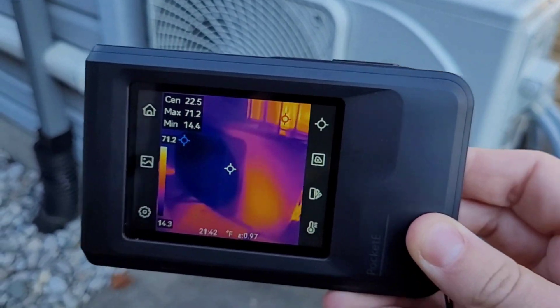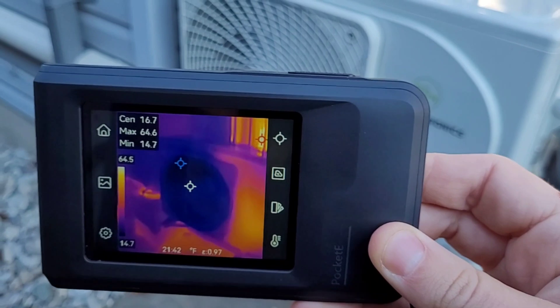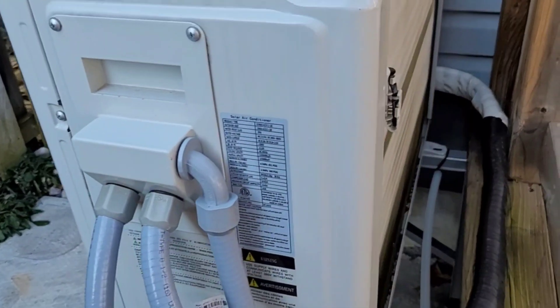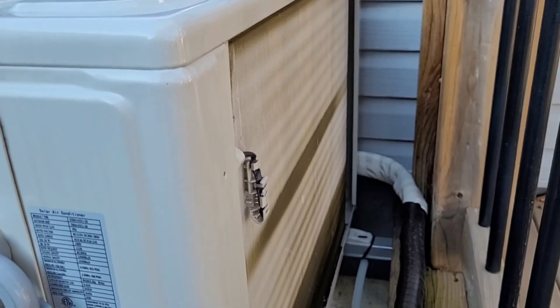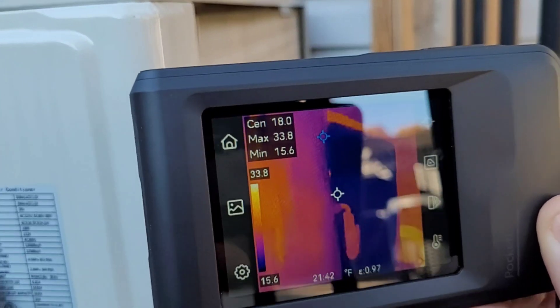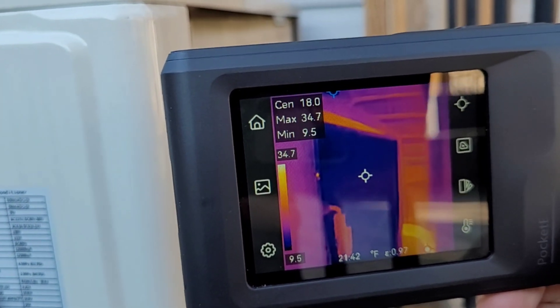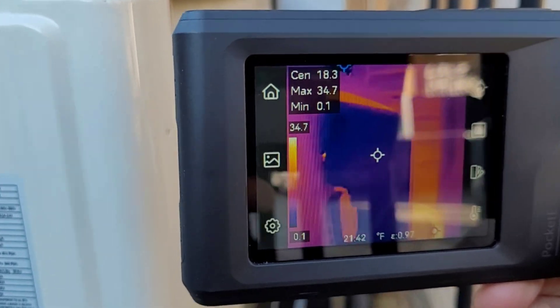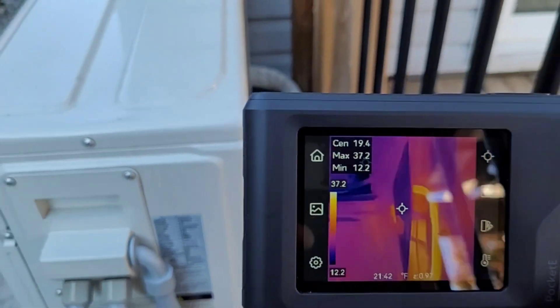For November I'm going to change the strategy a little bit. I don't think I'm going to be able to heat entirely on the heat pump — there were a couple days in October where it really struggled when it got really cold. As you can see today we're starting to frost the outdoor coil a little bit, and it's below zero today. So I'll take you inside and show you the power breakdown for the month, the indoor temperature, and what's going on with the indoor unit.